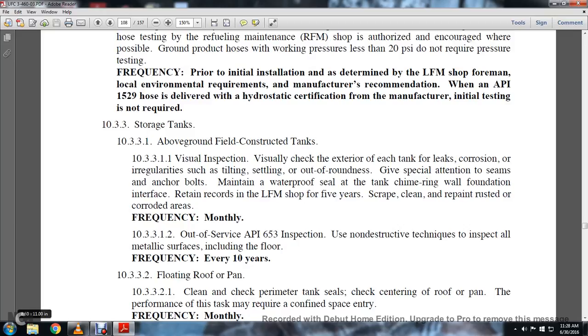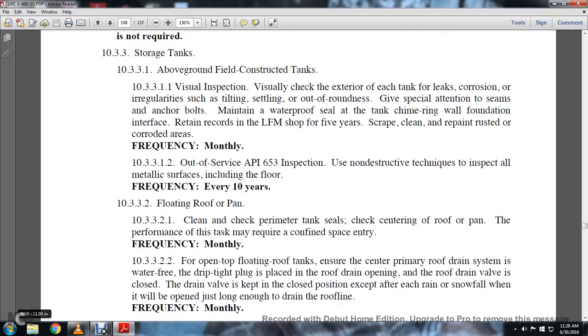10.3.3.1.2 Out of service API 653 inspection: use non-destructive techniques to inspect all metallic surfaces, including the floor, every 10 years. Floating roof and pan, 10.3.3.2.1: clean and check the perimeter tank seals, and check and clean the roof and pan. Performance of the task may require confined space entry. Frequency monthly. For open top roof tanks, ensure the center primary roof drain system is water-free. Keep the plug tight in place at the roof drain opening. The roof drain valve is kept closed except after each rain or snowfall, when it is opened just long enough to drain the roof. Monthly.